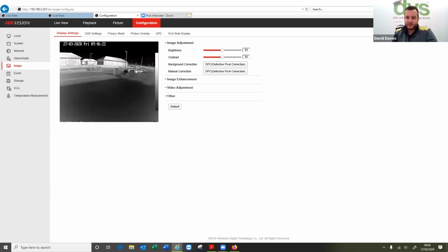Each camera can detect different ranges. So the T model has a different temperature range to this standard model. This standard model has a set temperature range of -20 to +150 degrees. The T model can go up to 550 degrees. So you've seen places like furnace control, coke making process, steel making process, and that kind of stuff, like factory foundries. We use them in that because the temperature range of this product doesn't suit. So by default, you need to use the T model anyway. So there's some background information on that.